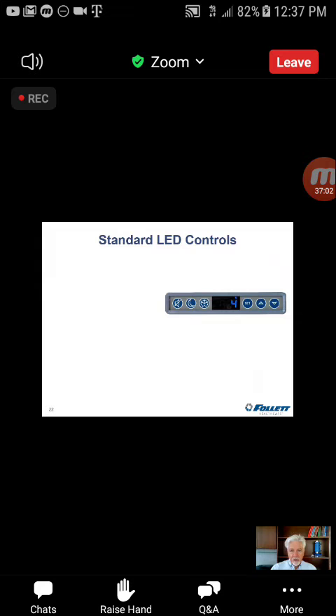And so let's go through those buttons one at a time. We'll start on the left-hand side. The first one, that speaker with a slash through it, is the mute button for the audible alarm. If the unit goes into alarm mode, there will be both an audible and a visual alarm. It will show that in the display as well. So if the staff wants to silence the unit, they can do that simply by touching that button on the far left-hand side. That will mute the audible alarm. If the alarm condition has not been corrected within 10 minutes, it will ring back.